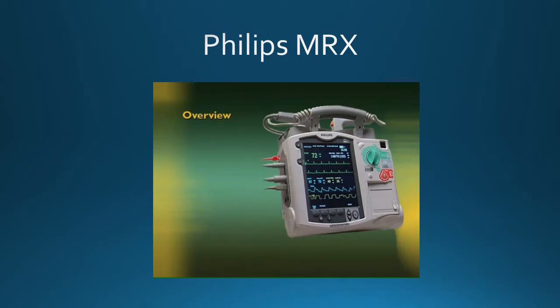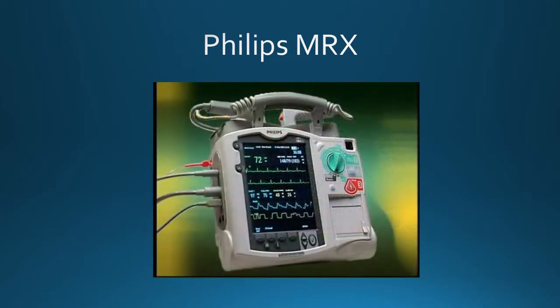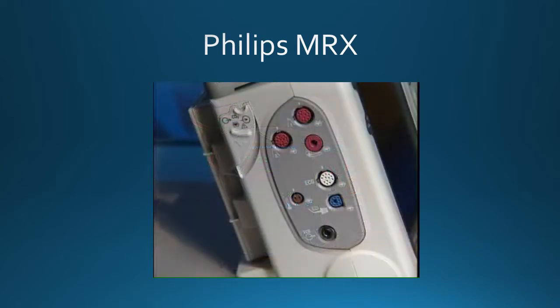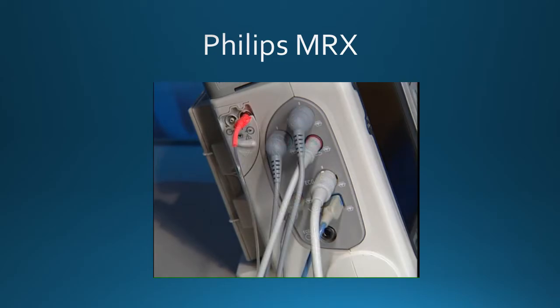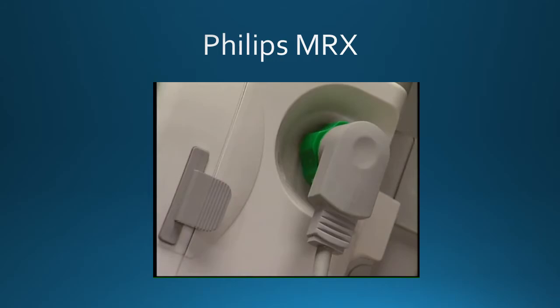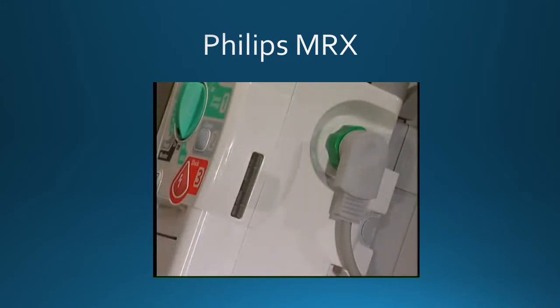Let's start with a look at the device's basic controls, how to use the ready-for-use indicator, battery operation, and how to perform operational checks. The MRX controls and connections are carefully organized to facilitate ease of use. Ports for monitoring cable connections are on the left. ECG, SpO2, non-invasive blood pressure, invasive pressures, CO2, and temperature cables plug in here. Therapy ports for paddles or multifunction electrode pads are on the other side. There's also a slot for a data card, so you can transfer patient information.